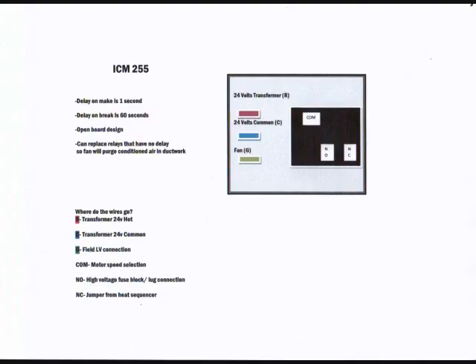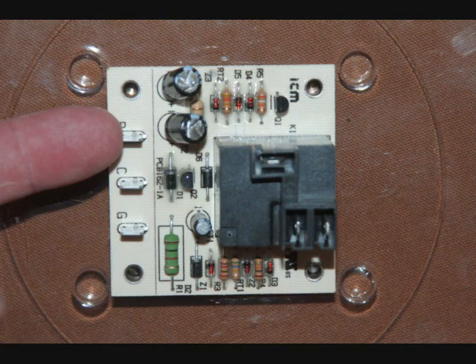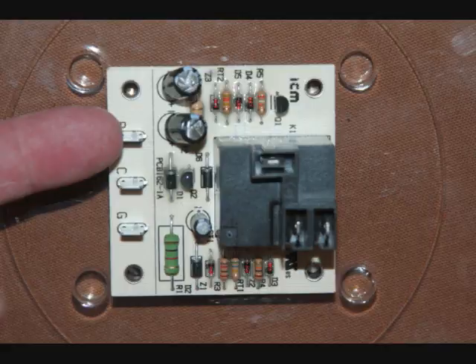The first thing we're going to look at is low voltage wiring. If you look up on the left side you'll see 24 volt transformer R. That'll be your red wire typically running back to the high voltage transformer or low voltage transformer hot. There is a location on the board of that wire. You would wire it right there.